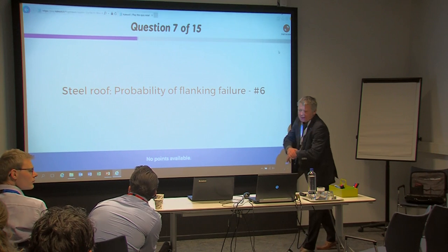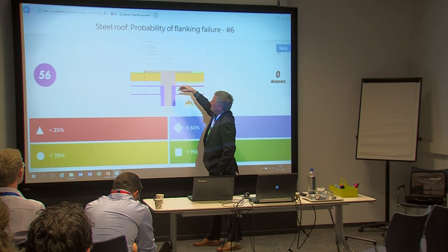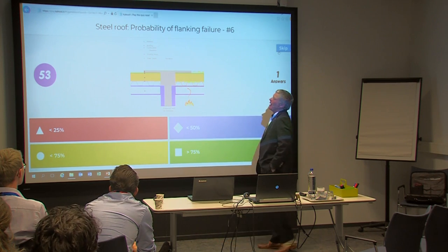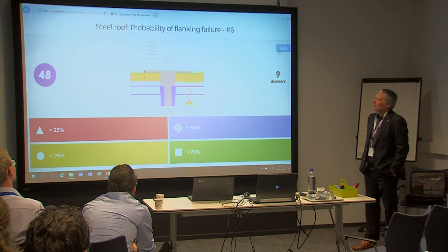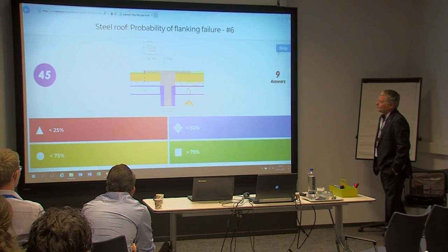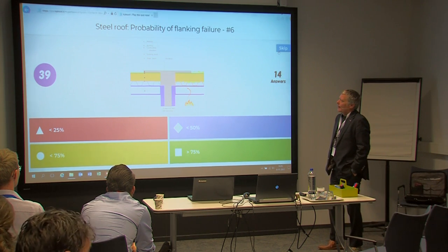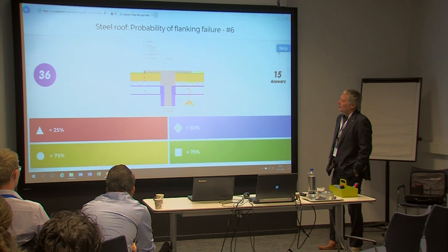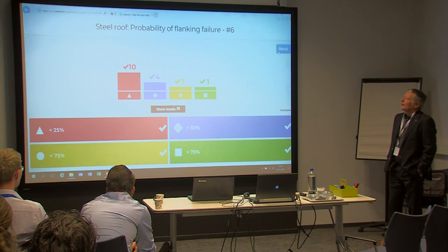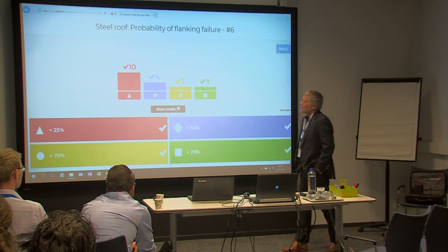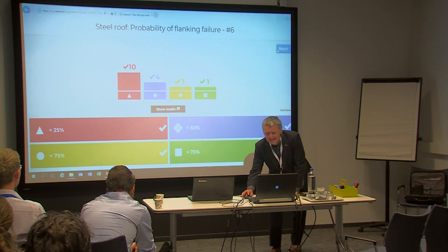The last roof detail is similar to the previous but with combustible layers and a real fire block, creating two separate constructions. Same question: what's the influence of flanking heat transfer along the compartment wall? Results show slightly less spread than the previous detail, which is remarkable.